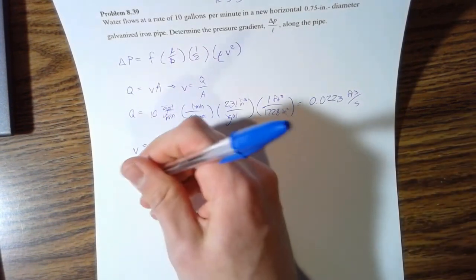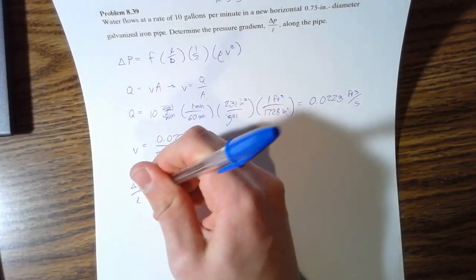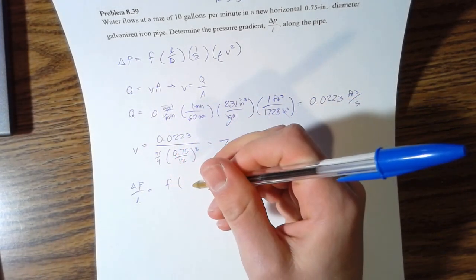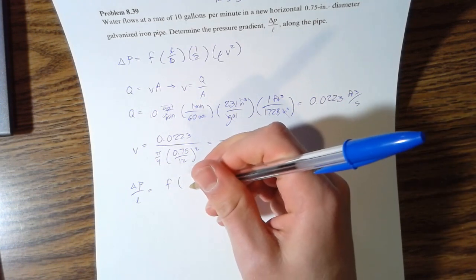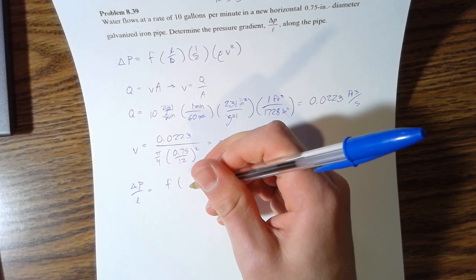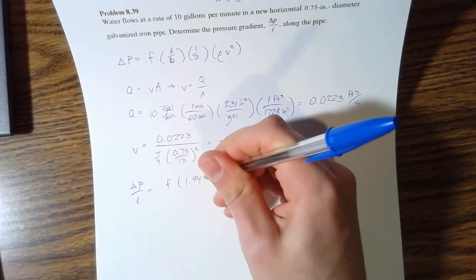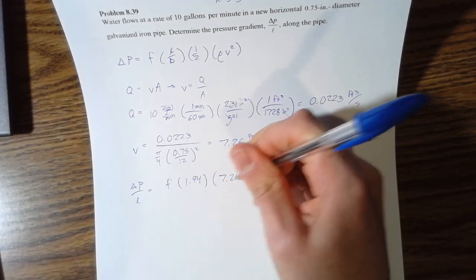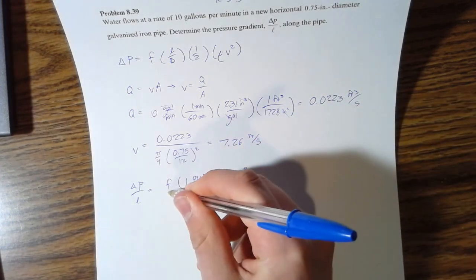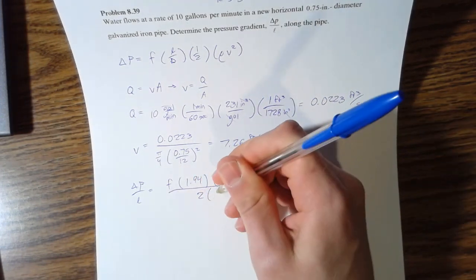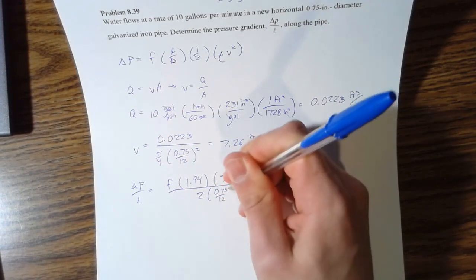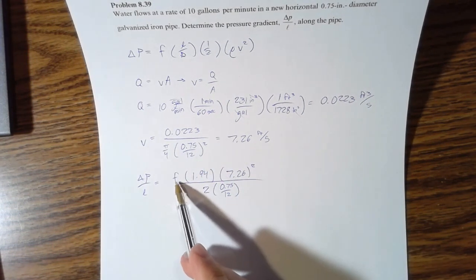So that's the velocity that we can use, and we'll go ahead and solve this equation for what we're actually looking for. So delta P over L is equal to that friction times the density of water, which is 1.94 slugs per foot cubed, multiplied by our velocity squared, which is 7.26 squared, divided by 2 times our diameter, 0.75 again over 12 because we want that in feet.